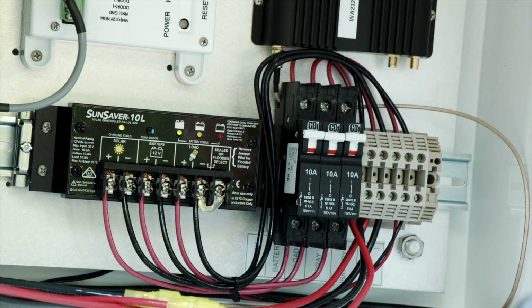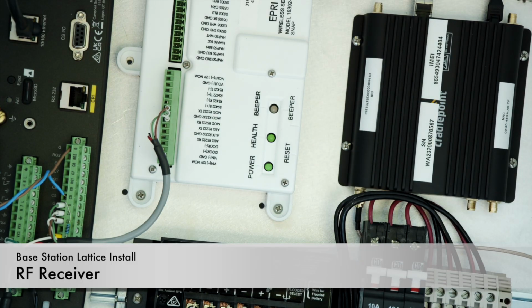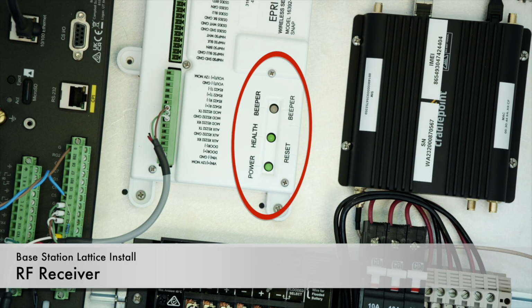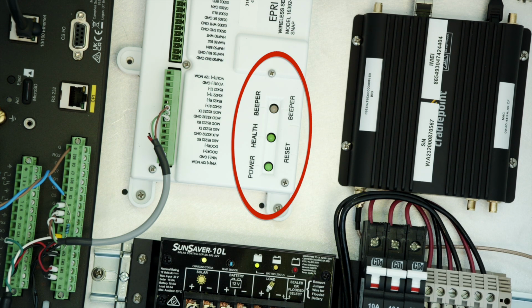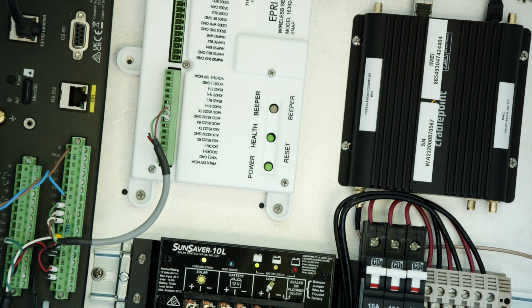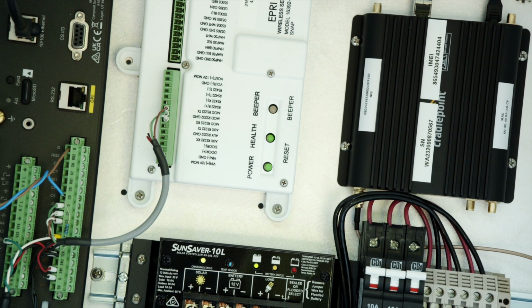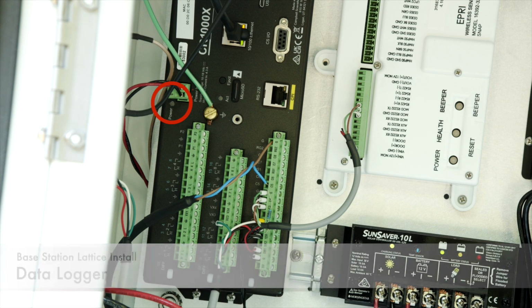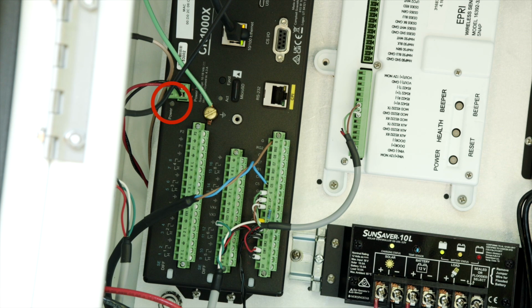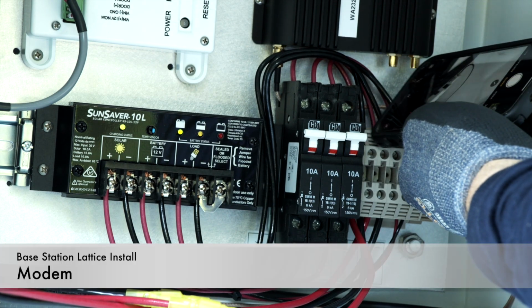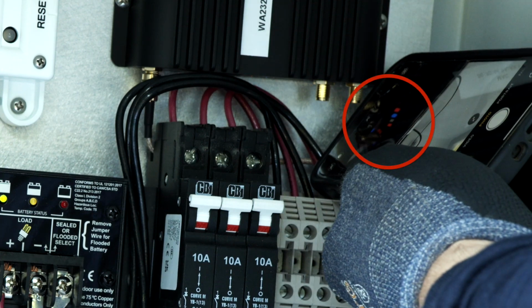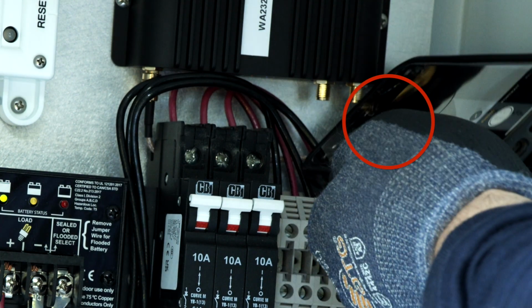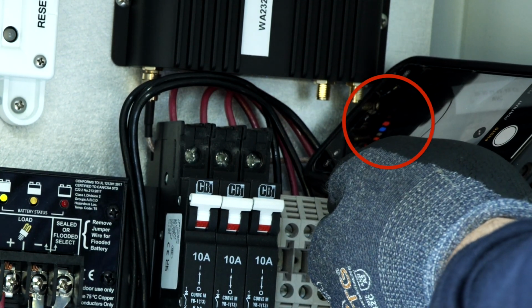Check the following status LEDs. RF receiver LEDs. The power and health LEDs on the RF receiver should be green. The LED may blink intermittently if the receiver is getting data from RF monitors nearby. Data logger LEDs. The red LED on the data logger should flash red on a regular interval every 10 to 30 seconds. Modem LEDs. The power and signal LEDs on the cellular modem will be lit when it's operating correctly. The signal LEDs indicate signal reception strength. Modem models may vary, and the LEDs could be difficult to see.